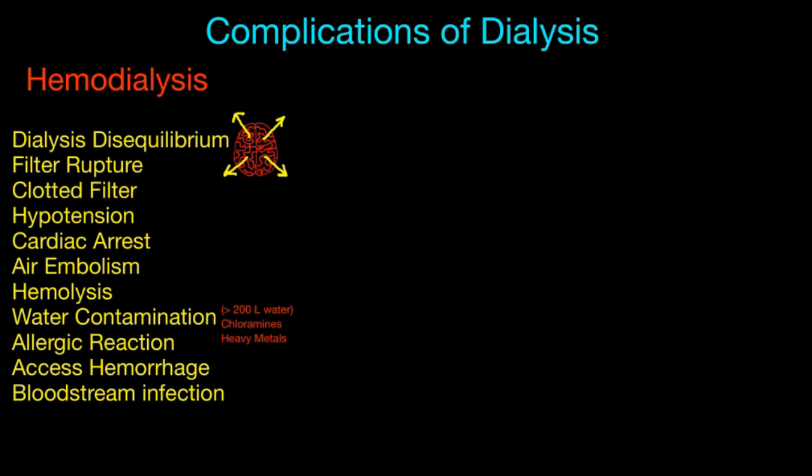That dialysate that I've mentioned in other videos is actually mixed on site with ultra pure water that is created on site at the dialysis unit. So you can't just use water that came straight out of the tap. Water out of the tap contains chlorine or chloramines that was used to purify the water, right? The city does that. But dialysate water is going to be in very close contact with your blood, and you don't want bacteria or endotoxins or other heavy metals or chlorine in that water.